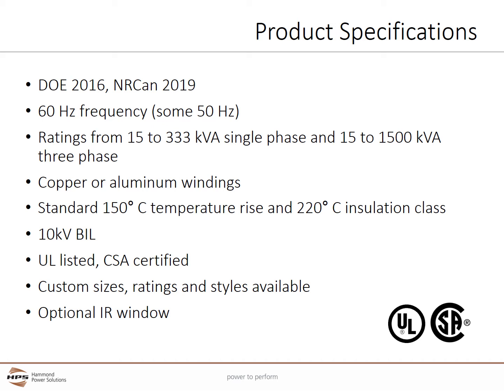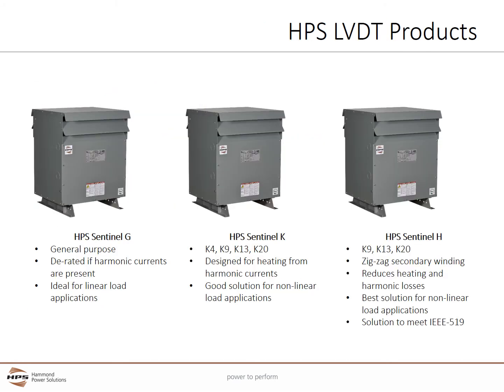Units can be ordered with an optional IR window. HPS has three separate Sentinel product lines. The Sentinel-G is a general purpose isolation transformer. It would have to be de-rated if harmonic currents are present. It is ideal for linear load applications such as motors, resistive heat, and some lighting.